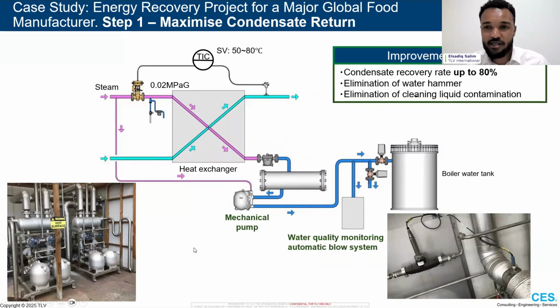So the solution should be split into two phases, and that's what was done on this site. Some images there to show some of the installation. So the first issue is the fact that we do not have enough pressure to return the condensate. So that's an independent issue on its own. And the solution is very clear. It's not just TLV who do this.